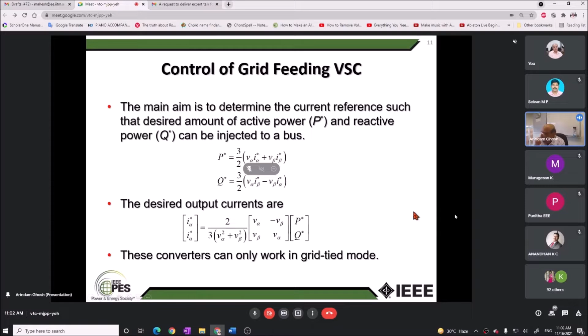Now, as I mentioned, grid supporting converters are used for islanded operation of microgrids. The input to these converters on the DC side comes from the DGs or DERs, whatever you call them. These converters are required to produce output voltages depending on active power, reactive power, voltage magnitude, and frequency.